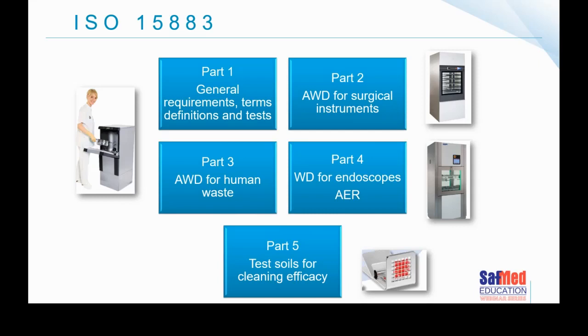The test soils are a combination of often egg-based material, dye, and sometimes sheep's blood, depending on the circumstances and the recipe. South Africa has adopted ISO 15883 — you can buy these standards electronically or in printed version off the SABS website. The parts currently adopted are part one and part two for automated washer disinfectors — requirements and tests for washer disinfectors employing thermal disinfection for surgical instruments, anesthetic equipment, bowls, dishes, receivers, utensils, and glassware. Part four, the latest version, was adopted in 2020.